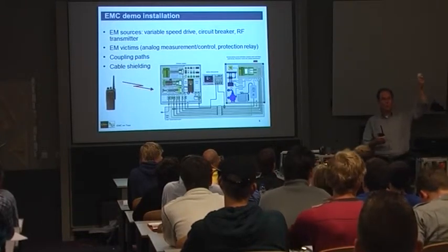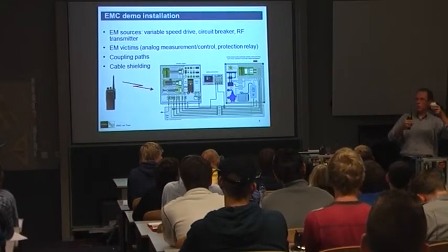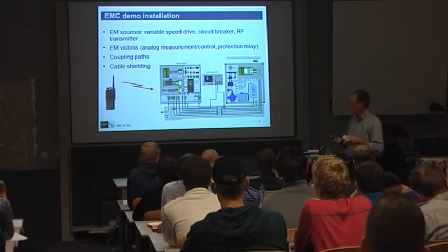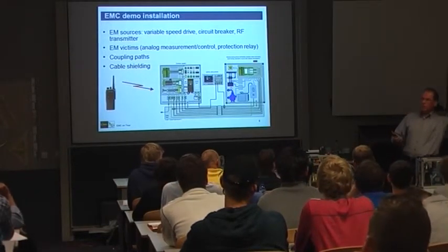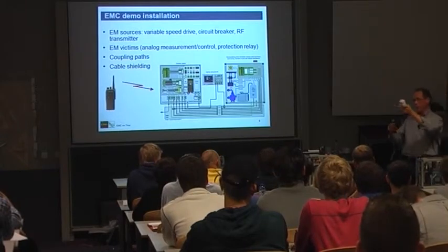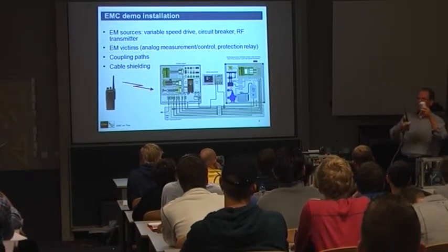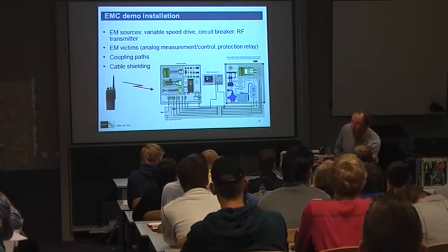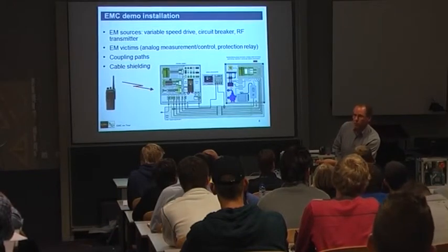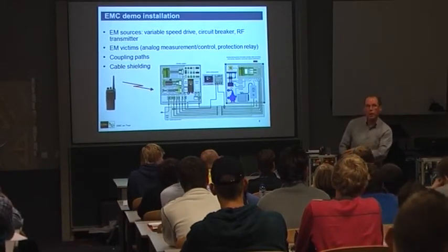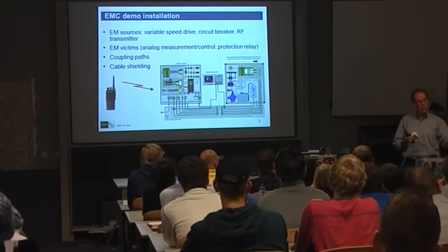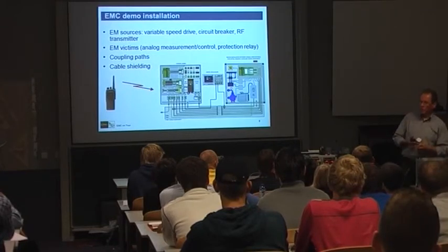So what happens? An idea. I've got fields, a cable. The cable, right. So this is the first learning point: if I don't have a cable, there's probably not an issue. The field is going to induce some noise current on the cable, which goes from the sensor to the PLC, the analog electronics. And there it's going to produce an offset in the working point of the transistor. It's going out of the limit that I've set in the frequency.